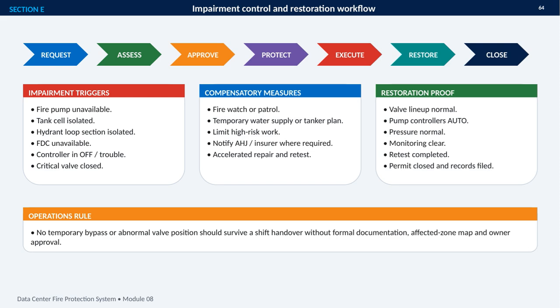Once identified, compensatory measures must be assigned. These may include a fire watch or patrol, a temporary water supply or tanker plan, limits on high-risk work, required notification to the authority having jurisdiction or insurer, and accelerated repair and retesting. Restoration is not complete until there is proof. Valves are back to their normal lineup, pump controllers are in auto, pressure is normal, monitoring is clear, and the retest is finished. The permit must then be closed and records filed.